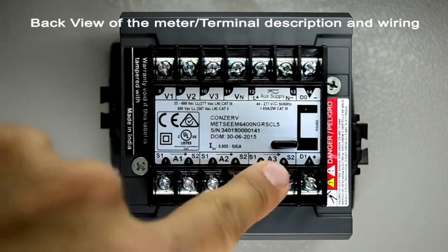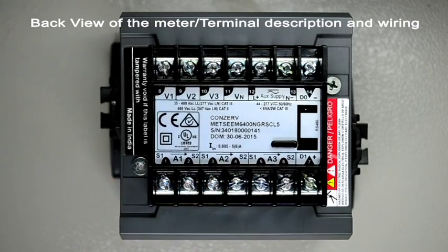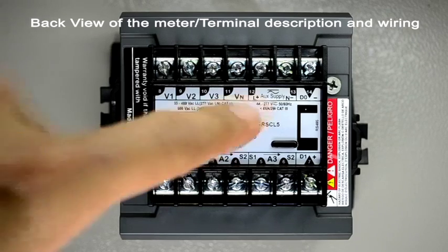A1, A2, A3 indicate the current terminals. For current terminals, S1 indicates in and S2 indicates out. Currents up to 5 amps can be directly connected to these terminals. Currents above 5 amps should be connected through external CTs rated for either 1 amp or 5 amp secondary.